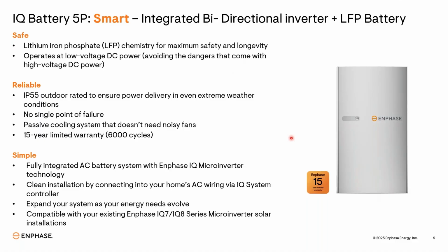There is no moving part inside this battery. Cooling is also passive, no fans. If a fan is there, noise will be there. And fans are the things which fail regularly. Why? Because of dust. Fans are used for the emission of heat. They keep your batteries cool, but they also attract nearby dust particles. With time, if you don't clean your fans, your fan will get choked. Once your fan is choking, it increases the temperature inside the batteries, and if it's not cleaned, it's going to fail. That's why we don't have any fans there. It's totally passive cooling.